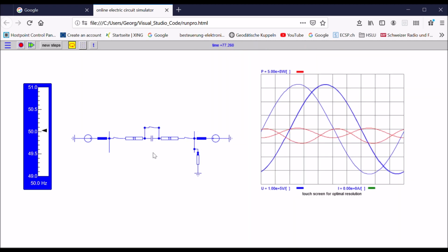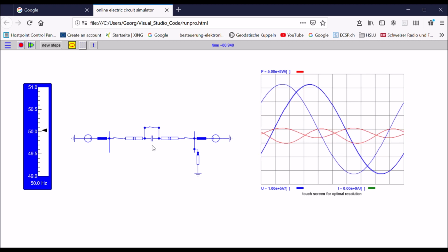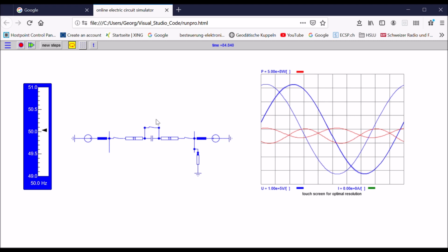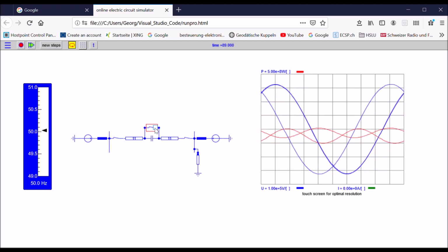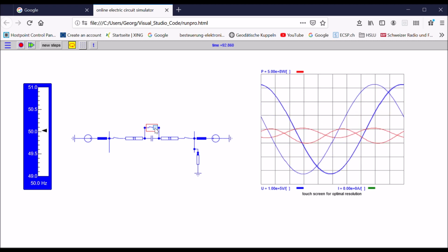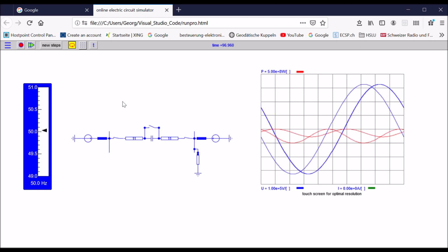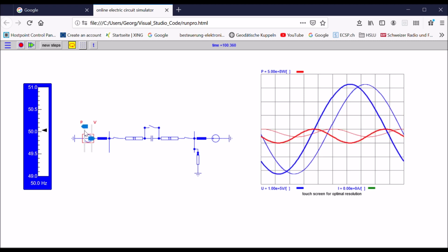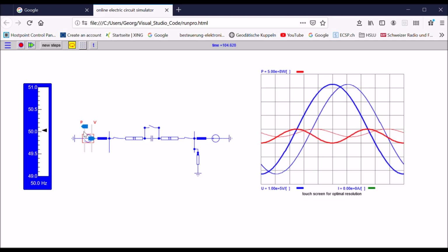I have now built this capacitor in the middle of the line, and you can see now what happens. Now the capacitor is short circuit, that means not effective. Now I remove the short circuit, and you will see how the phase angle difference between sending and receiving end is smaller. So you have now seen how it gets smaller. That means I can now, through the same line, still increase the power without putting the stability of the system in danger.